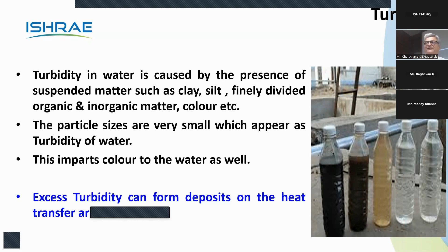This turbidity will play havoc when it is in the cooling water area. In the case of cooling water, excess turbidity can form deposits on the heat transfer area. Plus, it induces microbial contamination and issues in the cooling water circuit. So turbidity needs to be controlled completely and absolutely. TSS and turbidity are interrelated, in that turbidity also is a component of total suspended solids. But the particle size in the case of turbidity is very small, so unsettleable, unfilterable, that kind of thing.